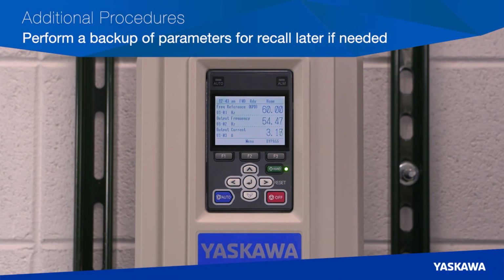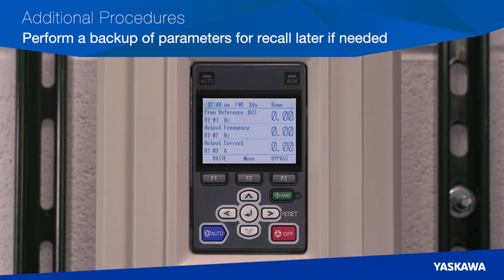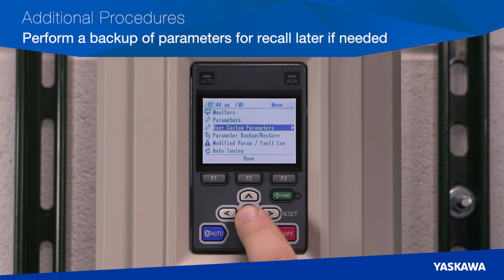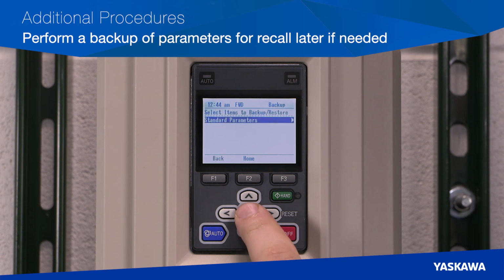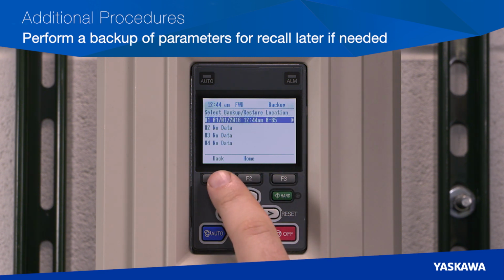If the application is operating as intended, you can opt to back up your parameters and settings to complete the startup. To perform a backup of parameters for your recall later if needed, go to the menu selection F2 and scroll to Parameter Backup Restore. Then select Standard Parameters, select Backup, and choose one of the 4 backup locations. Then verify your selection choice to save the parameter settings. If you are sure of your settings, select Yes. You will then be redirected back to the Backup Restore location menu with a time and date stamp for your saved parameters.